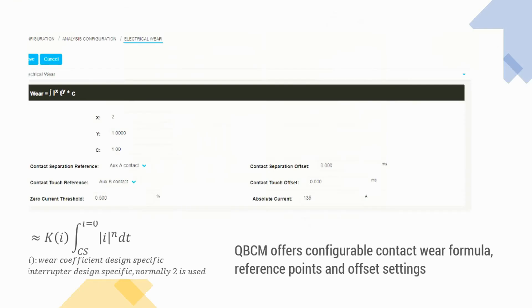I2T indicates the wear or stress on the arc contacts, which is one of the key information used in making decisions about breaker maintenance or replacement.